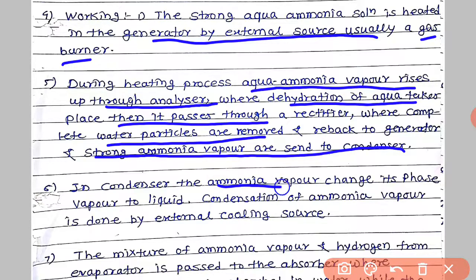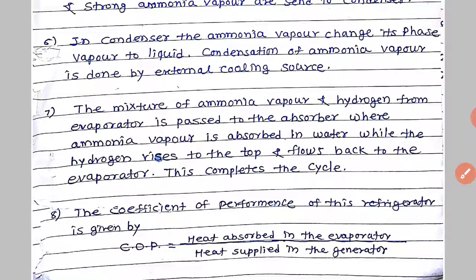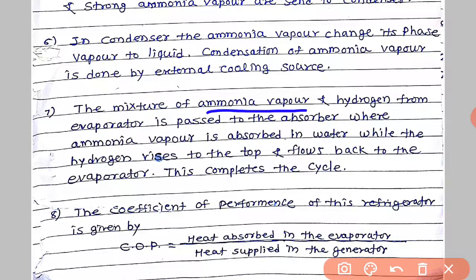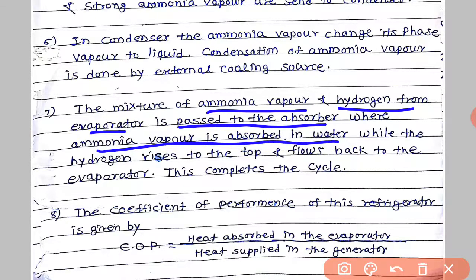In the condenser, the ammonia vapor changes phase from vapor to liquid. So liquid ammonia is supplied to the evaporator. In this process the condenser is cooled by using external sources or cooling water. So condensation of ammonia vapors is done by an external cooling source. Now the mixture of ammonia vapor and hydrogen from the evaporator is passed to the absorber, where ammonia vapors are absorbed in the water while hydrogen rises to the top and flows back to the evaporator.